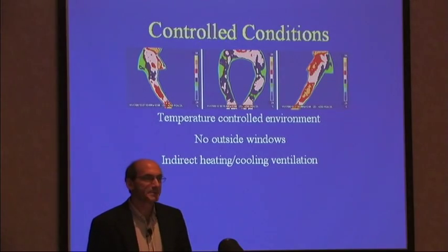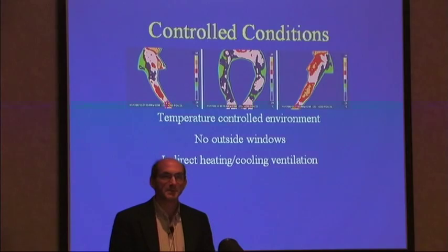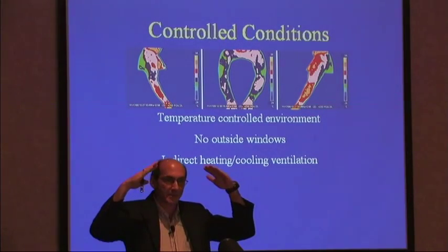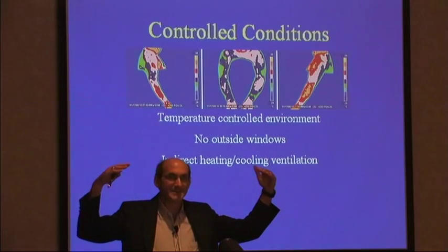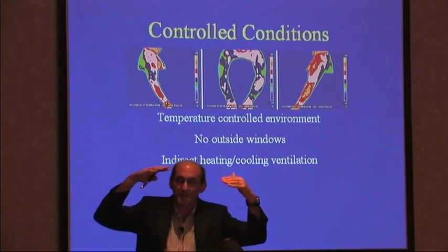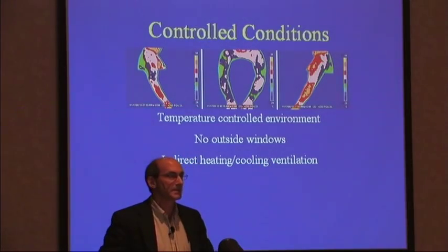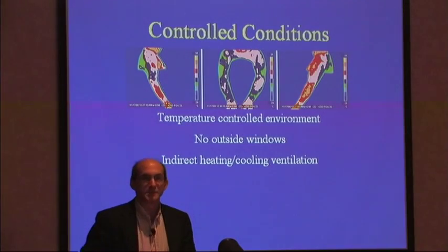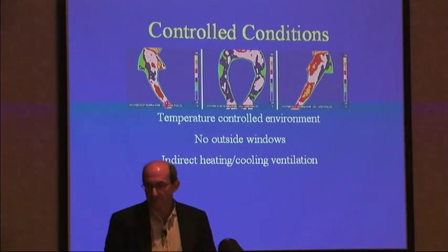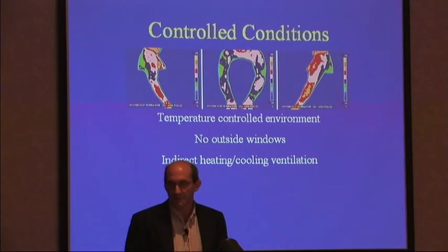We very much ascribe to controlled conditions. In fact, if you come to my office, you'll see that our thermal imaging room has its own HVAC. The vents come out of the ceiling, they don't blow on the patient, they go onto the ceiling and walls, and you can tell that that's true because the HVACs have their dust marks on them, and it goes off the ceilings and then down the walls, so there's no direct heating or cooling on the patient. There's no outside walls. You're not worried about infrared contamination from the outside. And we have a temperature-controlled environment.